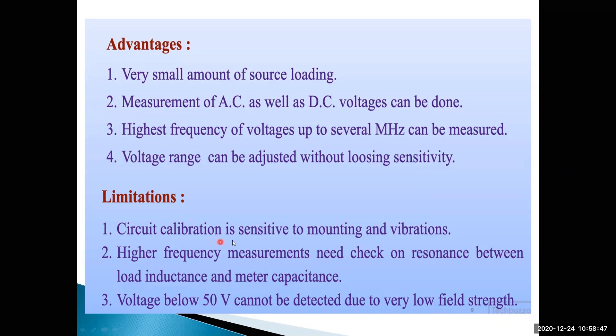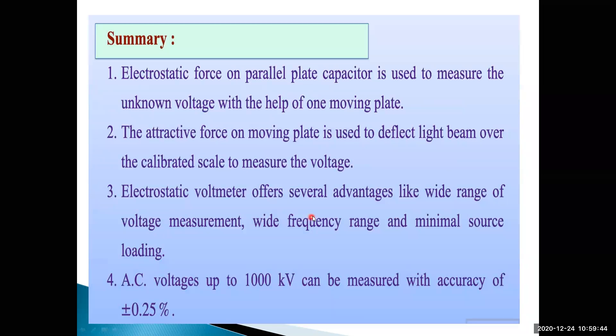Limitations: first, circuit calibration is sensitive to mounting and vibrations. Second, higher frequency measurements need a check on resonance between load inductance and meter capacitance - we must check the resonance condition each time. Third, voltage below 50 volts cannot be detected due to very low field strength.